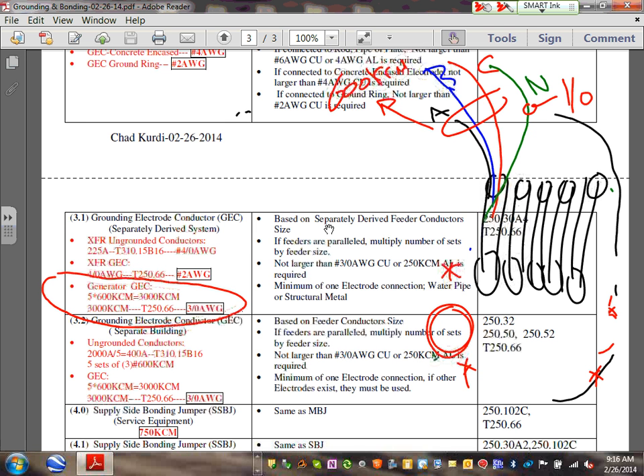Okay, so, gentlemen, you size it based on the separately derived conductor. If you parallel, you have to multiply, exactly like we did. You don't need to go larger than these two numbers, copper and aluminum. And at minimum, you need to tie to the water pipe or to the structure of the building. That has to go to the water pipe or the structural.